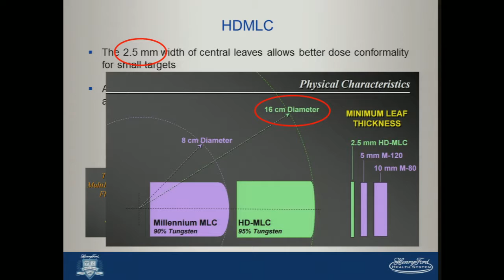Because this was a machine that was largely used for SRS SBRT, we opted to optimize for smaller targets there. Eclipse notably only allows 1 dynamic leaf gap value per beam model. Other treatment planning systems might allow more flexibility, so in that case you can probably optimize further. But just to mention that limitation. There's this nice presentation on the web from the Palo Alto Medical Foundation guys. They point out that you have the 2.5 millimeter inner leaves, and also on this particular HDMLC, they have increased the radius, the diameter of the rounded leaf tips to provide a sharper penumbra. So that's at 16 cm compared to 8 for the Millennium.